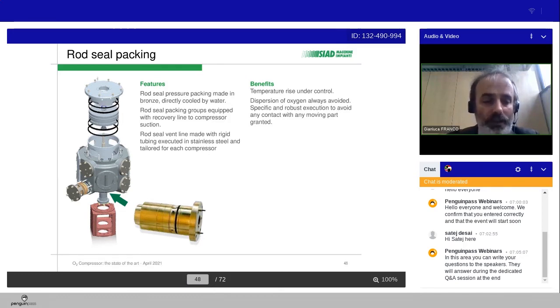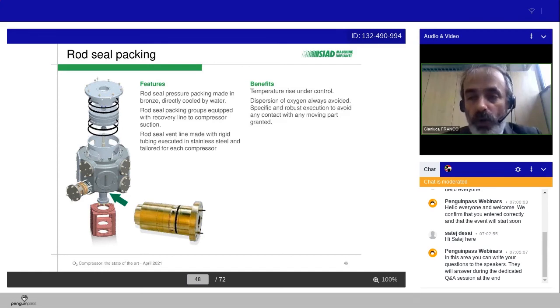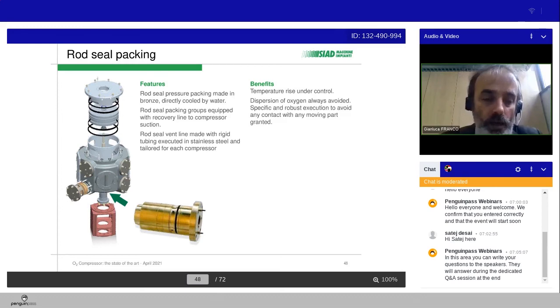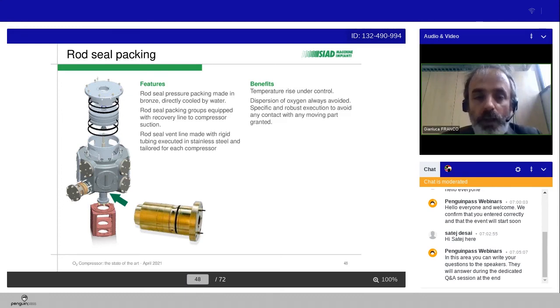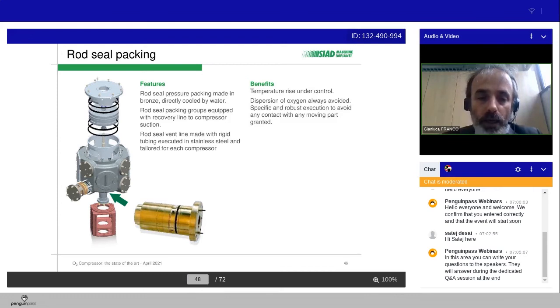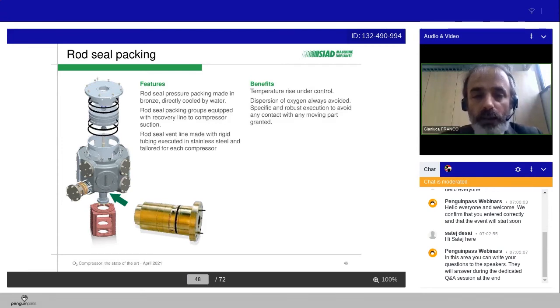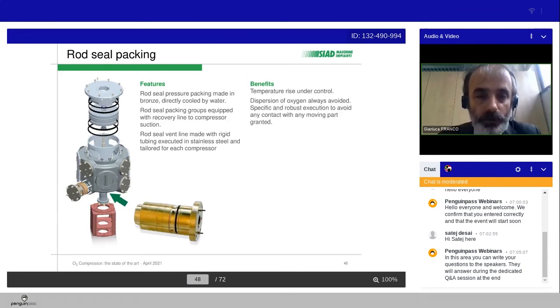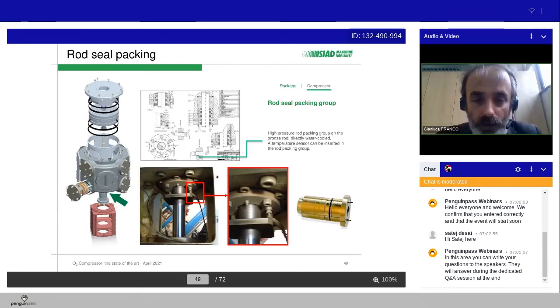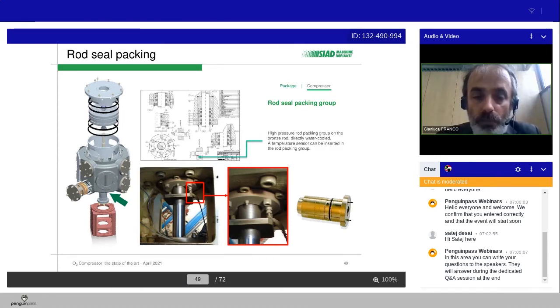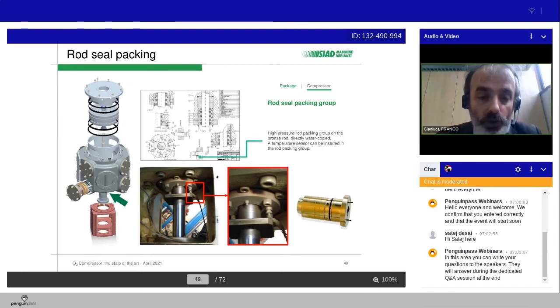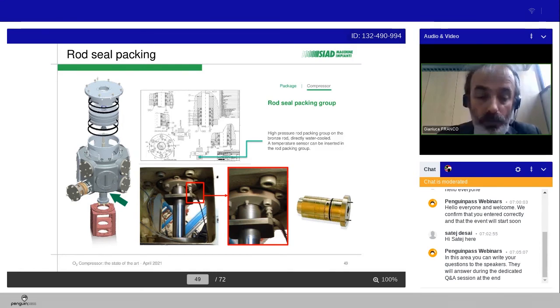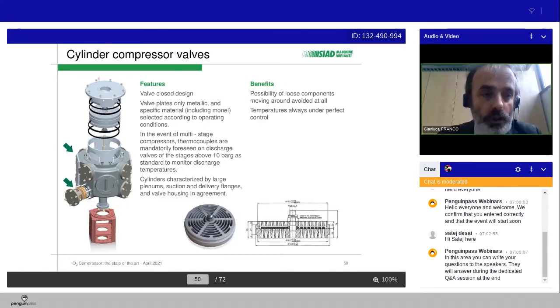The technical solution can be slightly modified customer by customer. Of course, the purpose of this solution is to get the temperature rise under control. In some solutions, it is possible that the temperature sensor can be inserted in the rod packing group in order to directly monitor the increase of the temperature and to avoid any risk of problems due to oxygen.